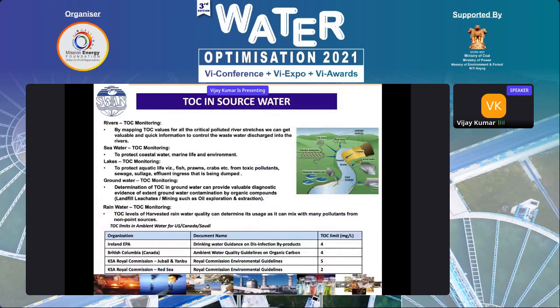When we talk about source water, TOC has a significant role in understanding what quality of water comes in, number one. Number two, it changes seasonally. Sometimes in the rainy season it will be different, in summer it will be different, and it also depends on what type of water you are receiving and what type of upstream activities are occurring. So how do you know? By measuring TOC periodically, you will know whether your water quality is good or not. That's why, for rivers, it is very good: it measures quickly, so you don't need to wait for a long time. That is the advantage here.